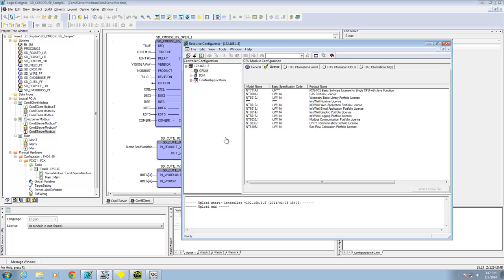The first step is to have a Stardom controller that actually has the Modbus Communication Portfolio license on it. To check what licenses you have installed, go to Resource Configurator, connect up to your Stardom, and then go to the License tab. You should see the Modbus Communication Portfolio license listed there. If you don't have it, and you have an FCN or FCJ, all licenses reside on the system card.